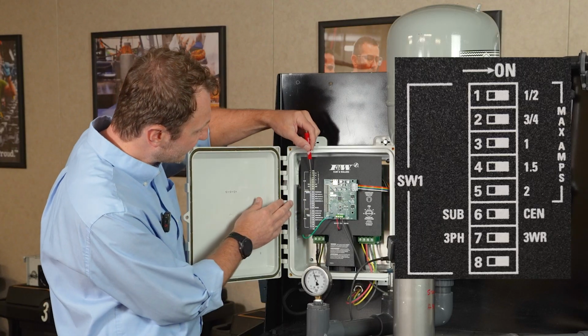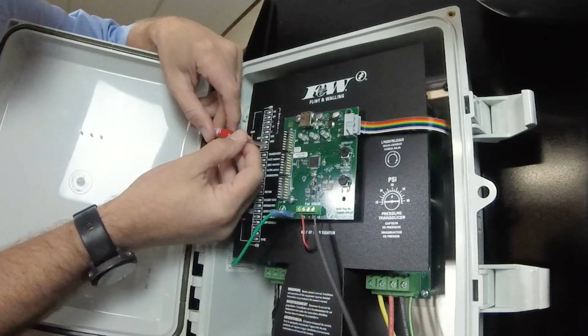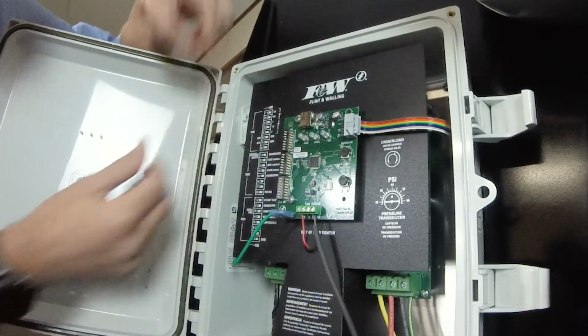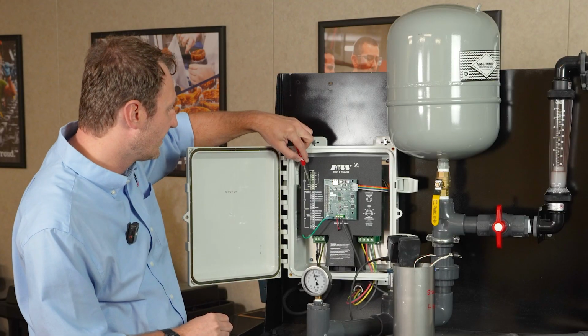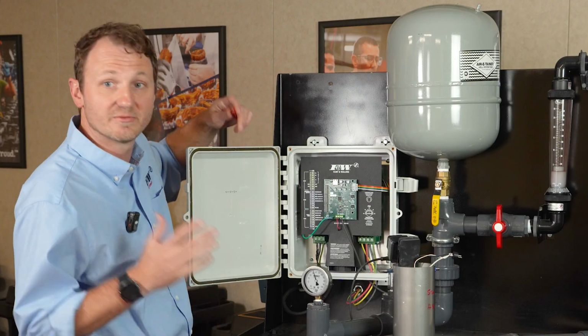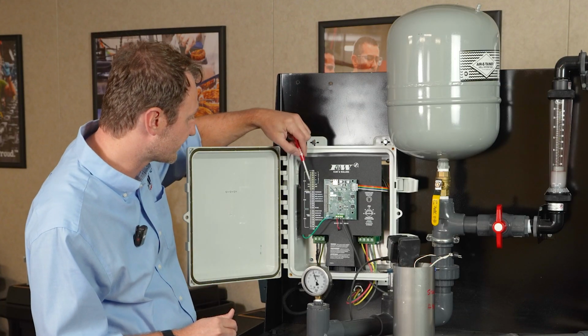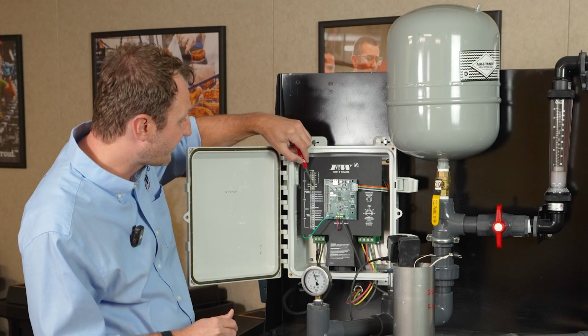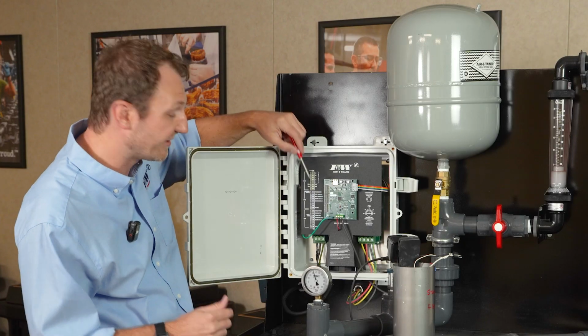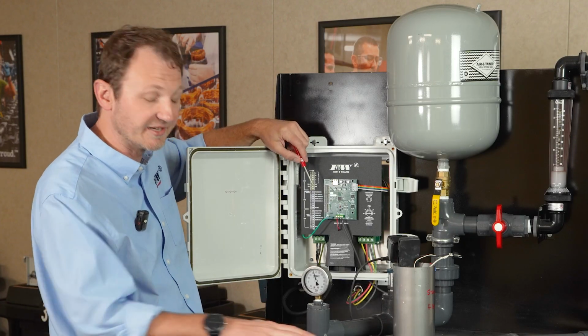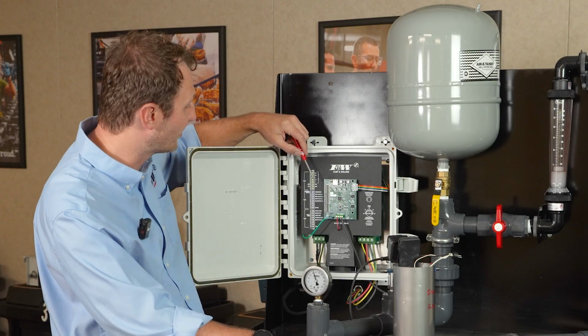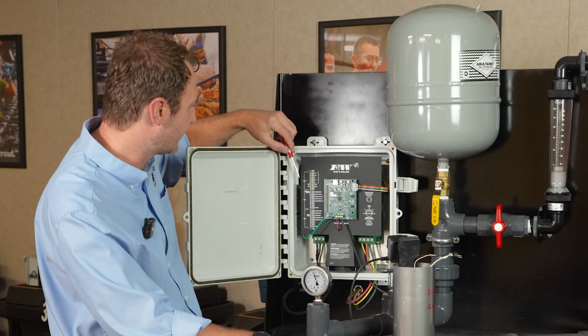So 1.5 horse here is number 4. So I'm going to go ahead and switch on number 4 dip switch just like this. So number 4 is on. Number 6, submersible centrifugal. I'm going to leave 6 on submersible. 7, 3-phase, 3-wire. Now 7 I can leave off in the 3-phase position. If this were a 3-wire single-phase motor, I'd want to turn 7 on.